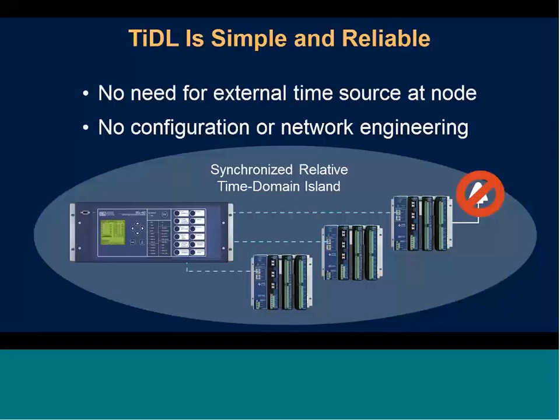Like I said, we essentially don't rely on time for protection. The relay can keep all of our nodes synchronized so they're sampling at the same time, so we don't have to have a time signal out to the field node. This is all done automatically by the relay—there's no configuration on the user's part to set up this time synchronization.